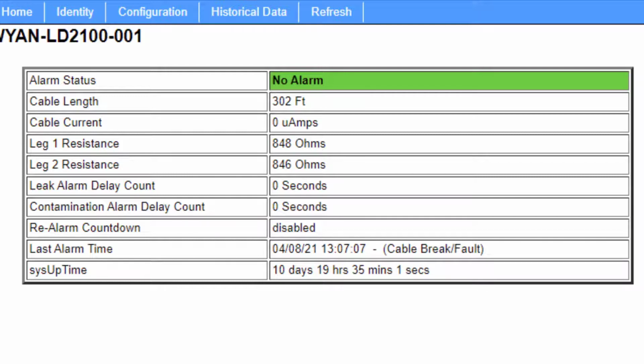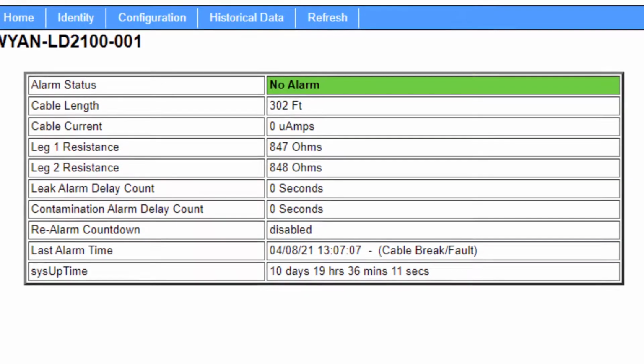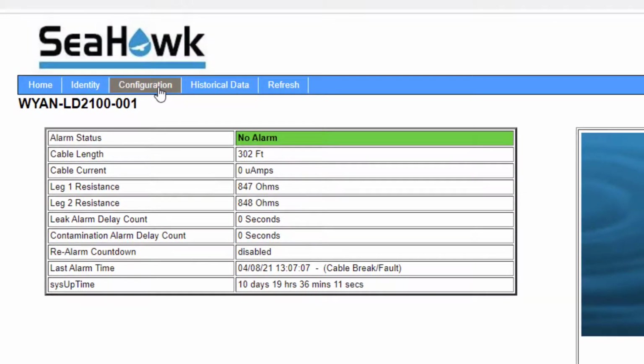So here on my screen, we can see I have 300 feet of physical cable, and I have a leg resistance of 848, and it's fluctuating up and down by a couple ohms. Once your cable's been installed and has come to the new ambient temperature, you can get a good reading. On here, since it keeps jumping up and down, I'll just base it off of 847 ohms being the average. So if we divide that 847 by 300 feet of physical cable, we come out to 2.823 ohms per foot.